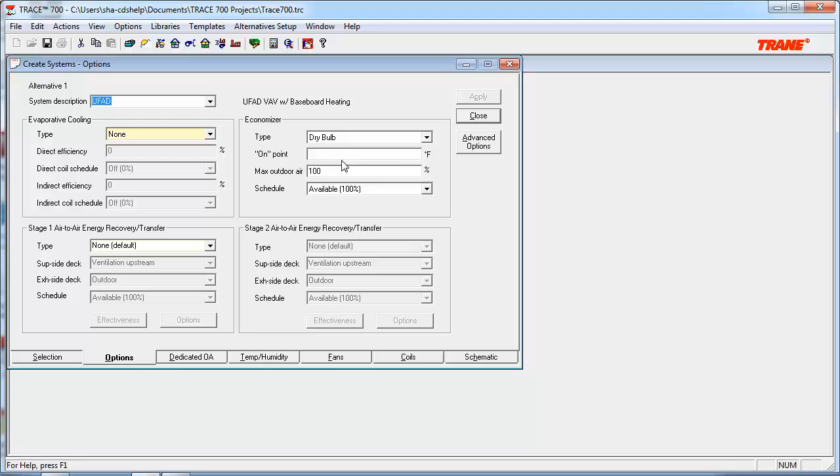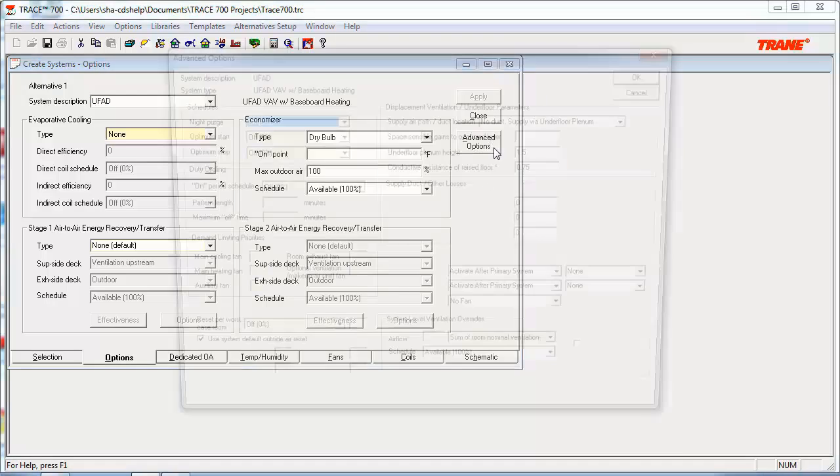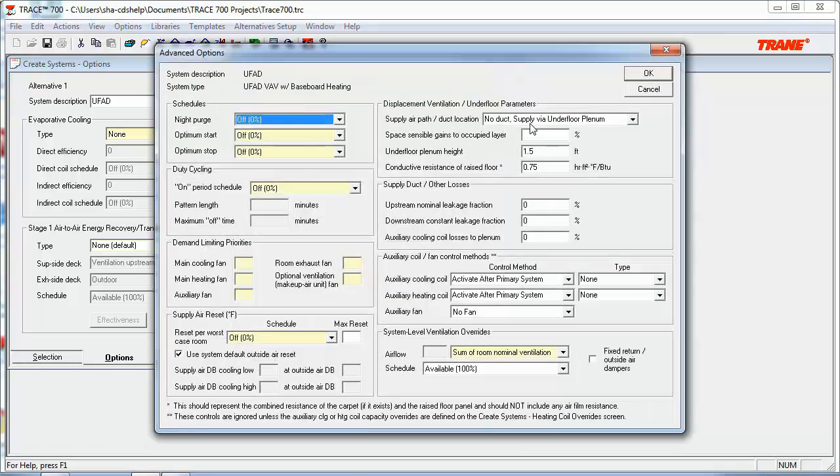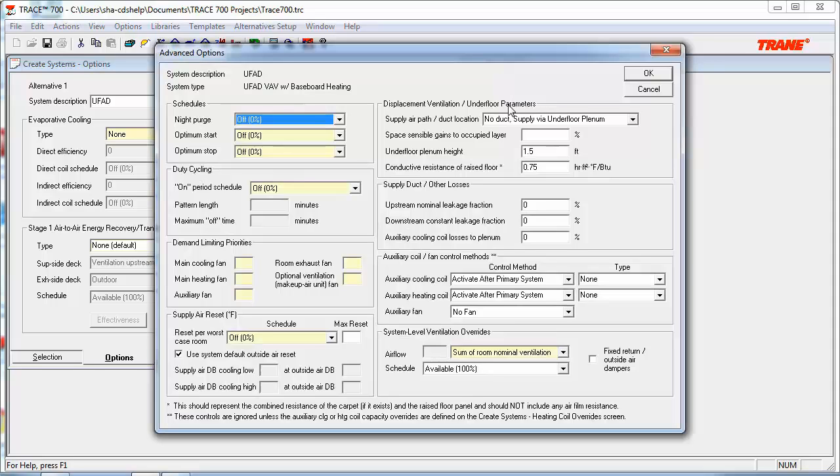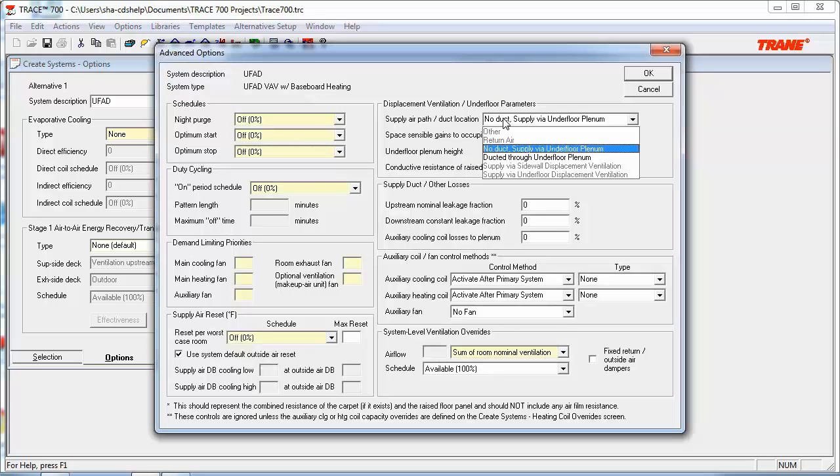Next, let's look at some other parameters here in the Advanced Options section. You'll see here in the top right that we have a section related to Displacement Ventilation slash Underfloor Parameters. So the first topic of consideration here is deciding where the incoming supply airflow is. So in this case, we'll look at the Supply Air Path slash Duct Location input. If no duct, supply via underfloor plenum, or supply via underfloor displacement ventilation is selected, heat transfer between underfloor and space will occur. However, if ducted through underfloor plenum, or supply via sidewall displacement ventilation is selected, no heat transfer between the underfloor and space will occur.